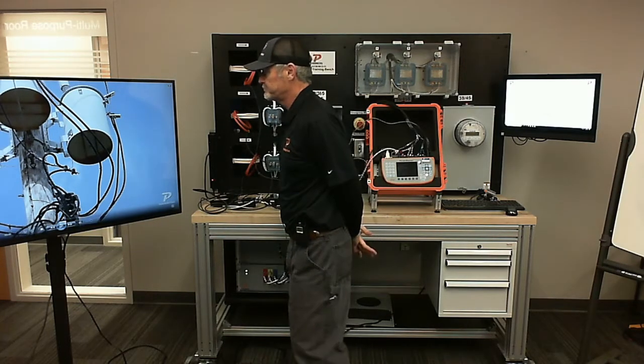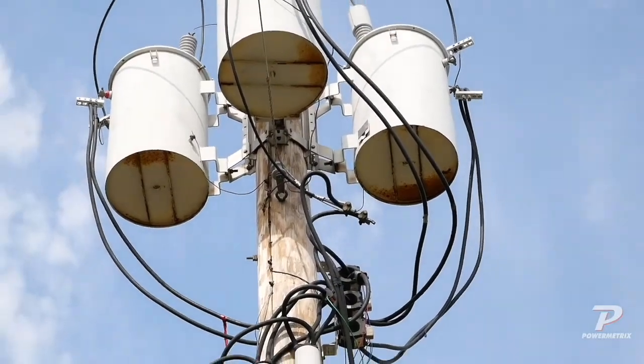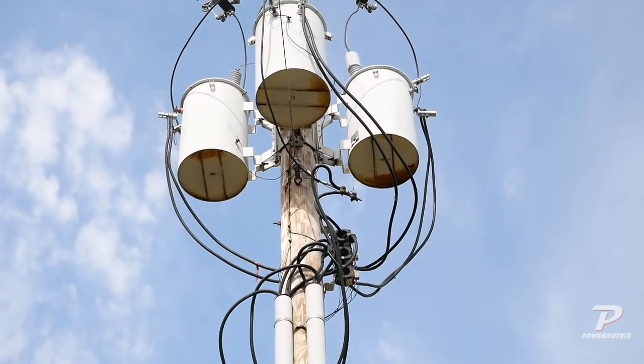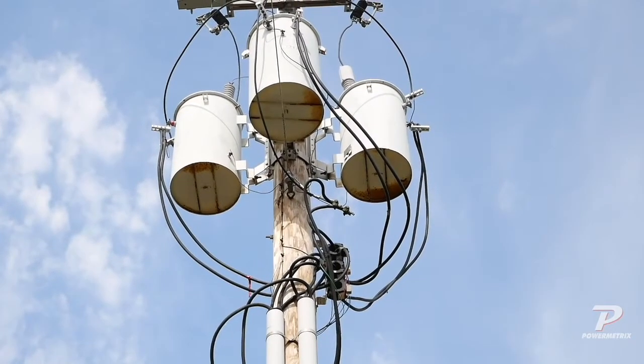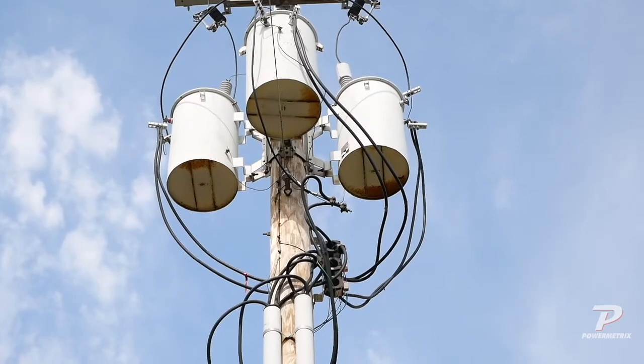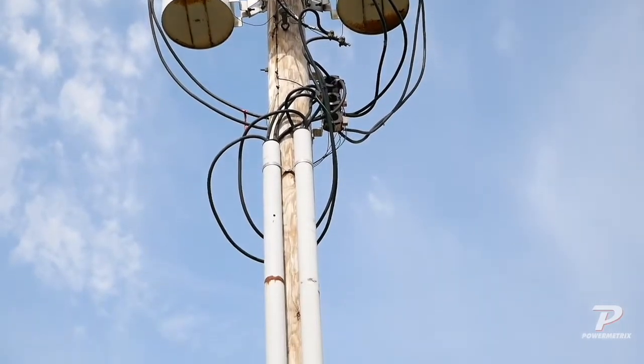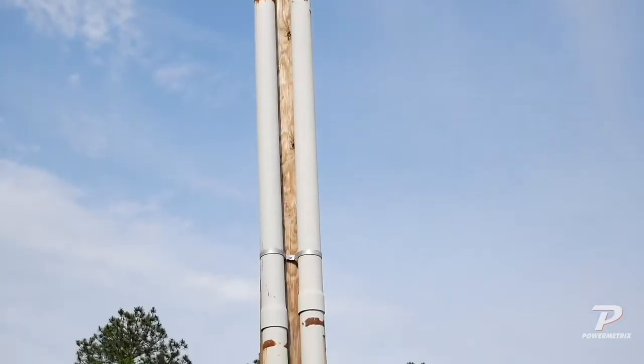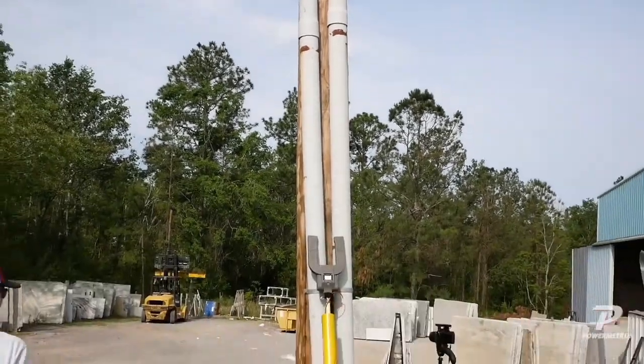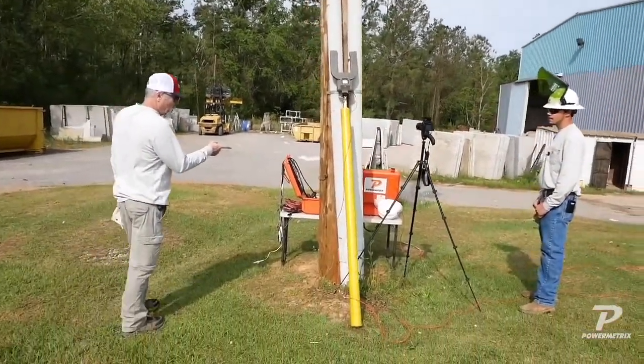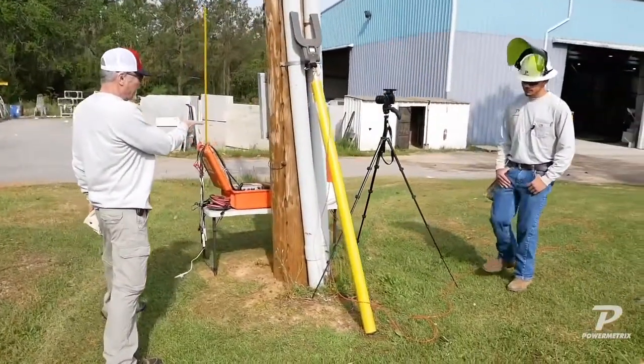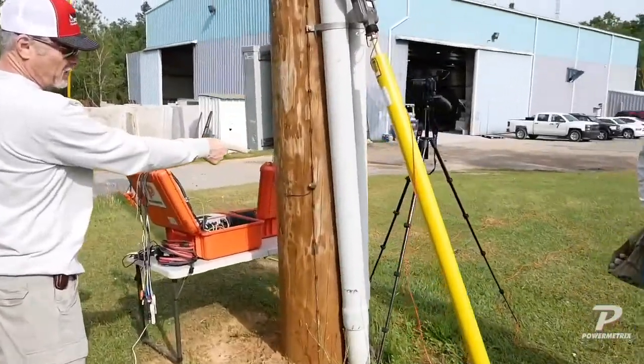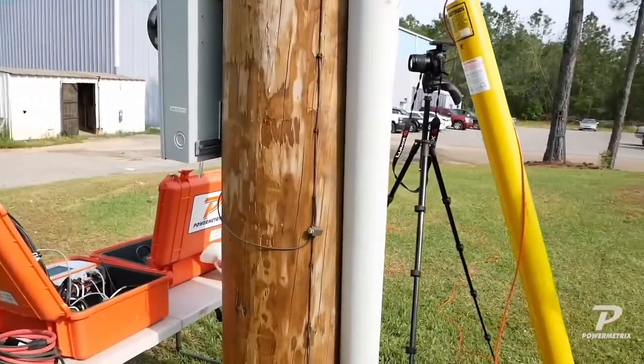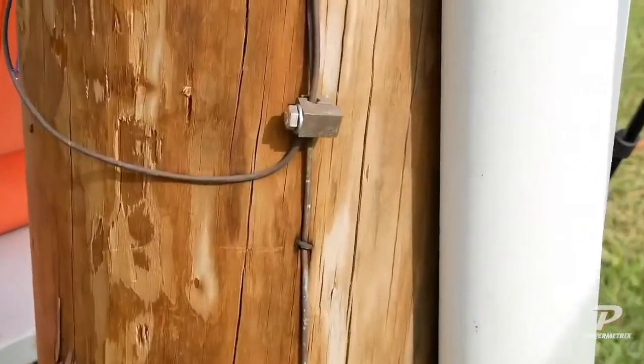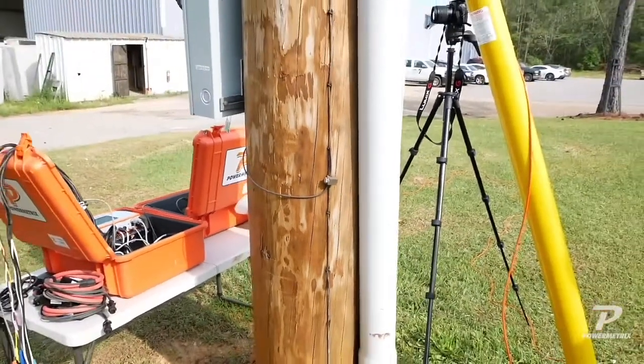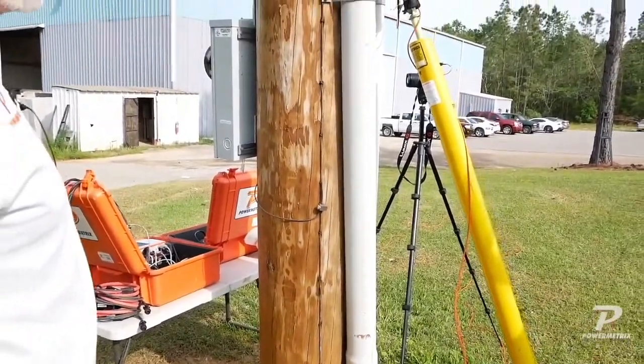Any trash or anything like that? Nothing up in the CTs like we've seen on some other sites. So far so good. Working our way down the pole, nothing too bad on the conduit here. We've got a good connection to our pole ground right here from the can - looks good. We're connected over here to the pole ground too, and we checked that - it was a snug connection, not loose.